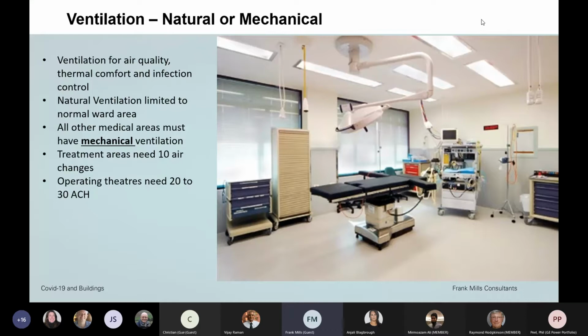Treatment areas, and people can see these numbers in our hospital guidance, NHS HTM03, need 10 air changes. So it's quite a high air load, quite a high cost, to supply a system that will deliver that. But at that kind of air change rate, the dilution effect is such that we could keep COVID down if it was being admitted into the air there.